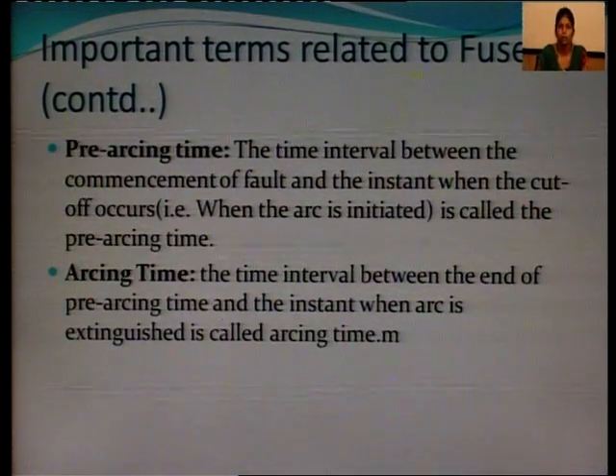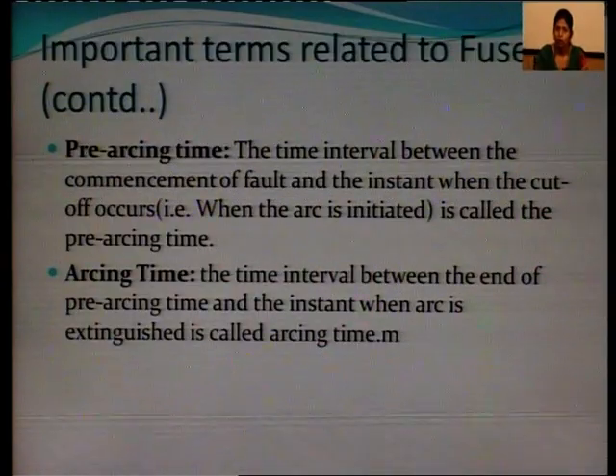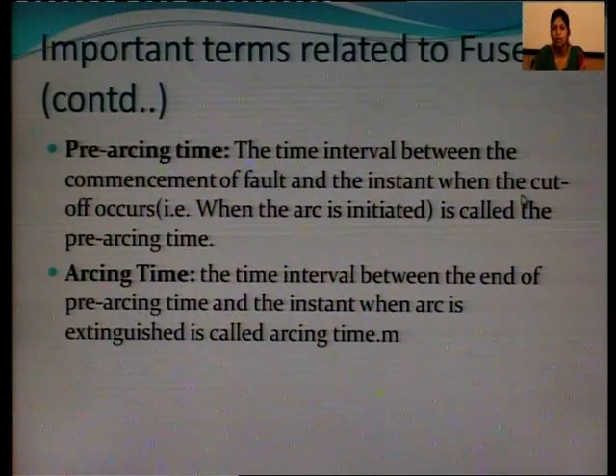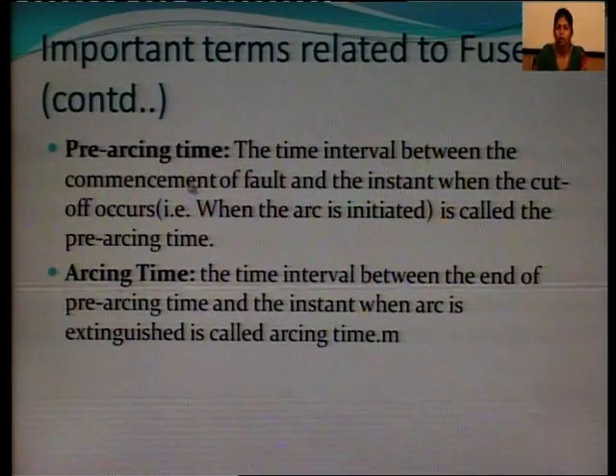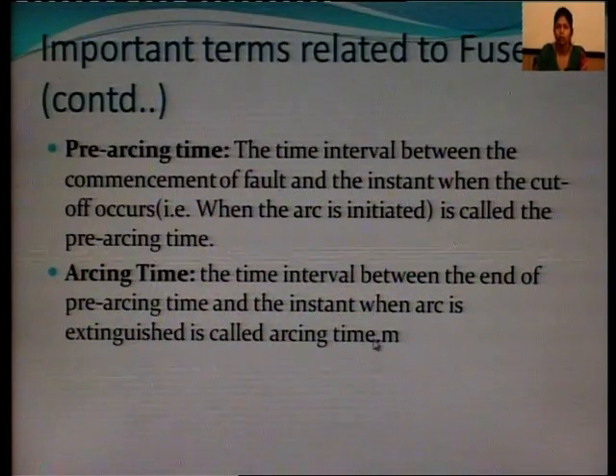Next is pre-arcing time: the time interval between the commencement of the fault and the instant when the cut-off occurs. So pre-arcing time is the time from when the fault occurs to the instant when cut-off happens. And arcing time is the interval between the end of pre-arcing time and the instant when the arc is extinguished, called the arcing time.